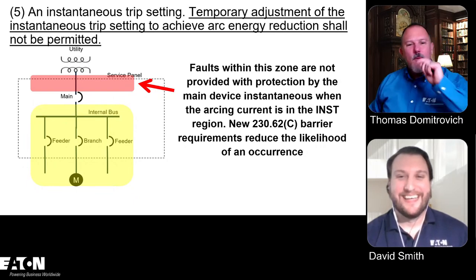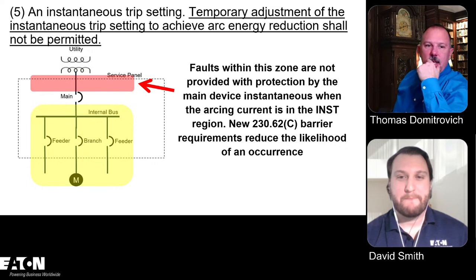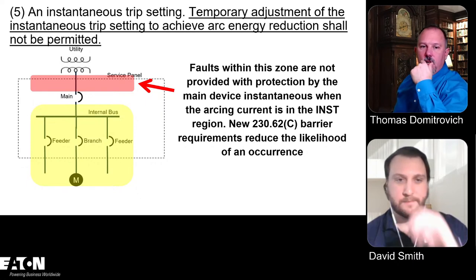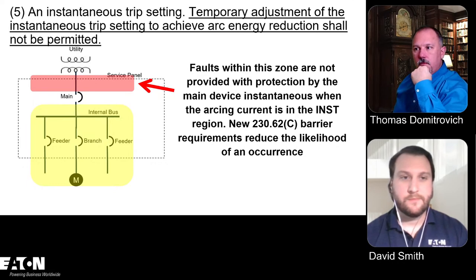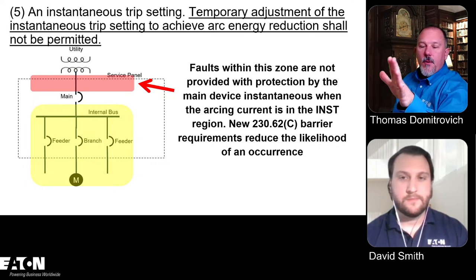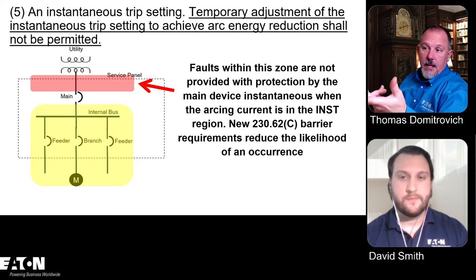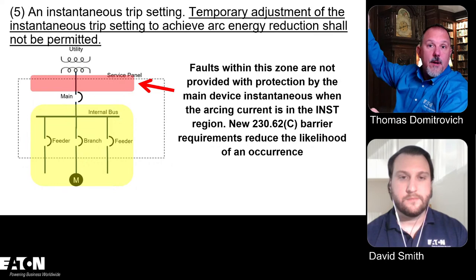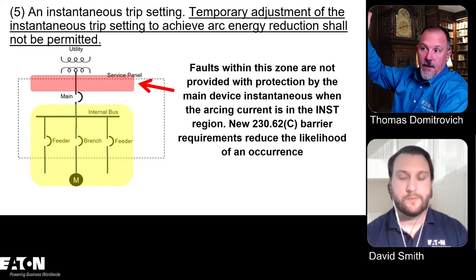All right, Ross. Let's think about this. The 240.87 requirement on main breakers. Remember, if you don't have a main breaker, let's say that what I'm showing on the screen here is a main breaker in a panelboard. If you don't have a main in the panelboard, you have a feeder upstream feeding the panelboard. If that feeder is 1200 amps, then this applies. Remember, this applies to the circuit breaker.